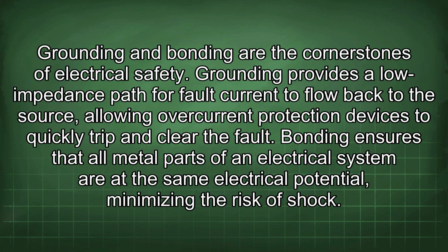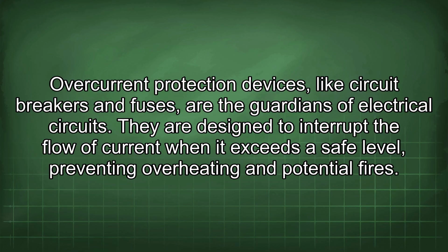Grounding and bonding are the cornerstones of electrical safety. Grounding provides a low impedance path for fault current to flow back to the source, allowing overcurrent protection devices to quickly trip and clear the fault. Bonding ensures that all metal parts of an electrical system are at the same electrical potential, minimizing the risk of shock.